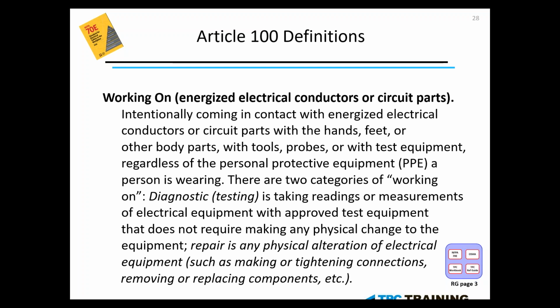So I brought this up mainly to identify the fact that you don't necessarily have to be working on a piece of equipment with the panel open or sitting inside a piece of switchgear with that hazard to be there. Sometimes it's as simple as just taking a diagnostic test and using your meter to take a measurement, or making an adjustment to the equipment. That is all considered working on. And this leads to the mindset that while working on something, we must protect ourselves if we cannot eliminate the hazard.